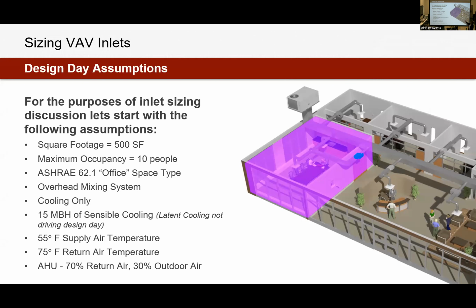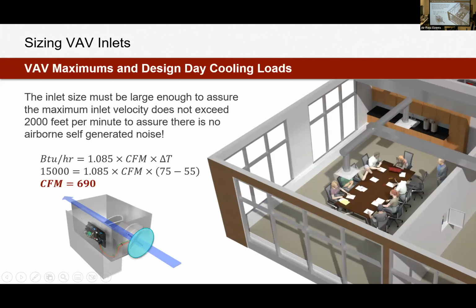Associated with every type of space, there's always a square footage and a number of people that we're sizing that space for. When we're starting to go through and pick our airflows, we need to be concerned with a couple of different points. Our maximum cooling airflow: at maximum load, how much cooling airflow are we going to need to provide to the space? We're concerned with our minimum airflows because we need to meet minimum ventilation requirements in the space. And then heating would be another concern, but for this example we are only going to be looking at cooling. So an engineer would use load calculation software and determine what the total amount of cooling load would be needed in the space. And then we can go about finding our airflow.